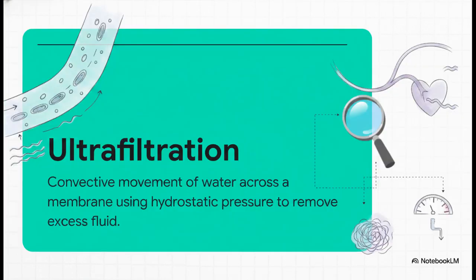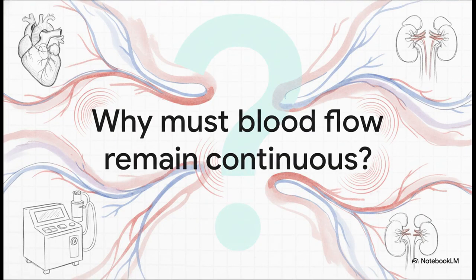Now, to handle that deadly fluid overload we talked about earlier, the machine uses a really precise process called ultrafiltration. It essentially relies on exact hydrostatic pressure, using fluid dynamics to literally push the dangerous excess water across the membrane and out of the body. But it is a delicate balance, guys. If the machine removes this fluid too quickly, the patient can experience severe muscle cramping and really dangerous drops in blood pressure.